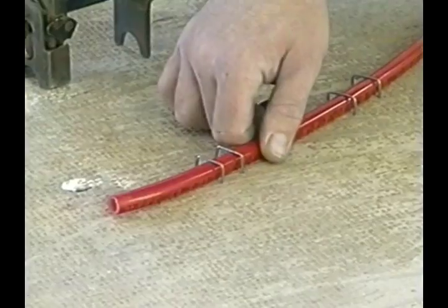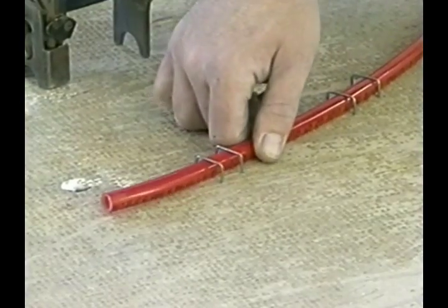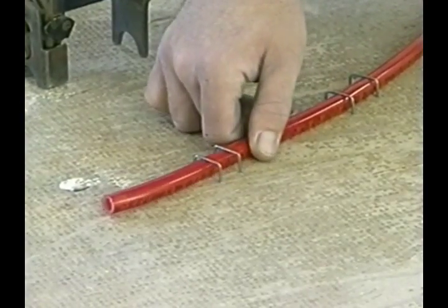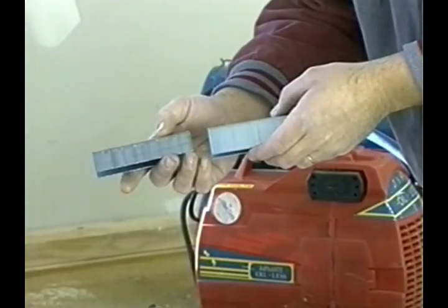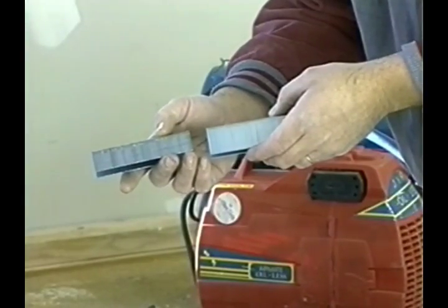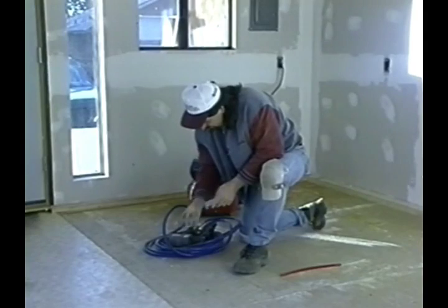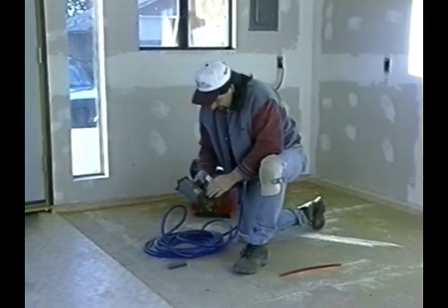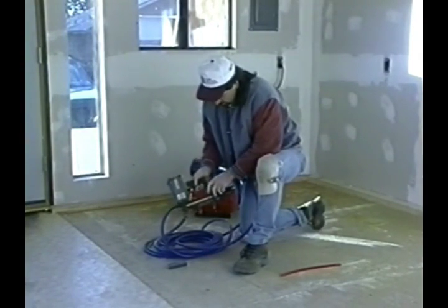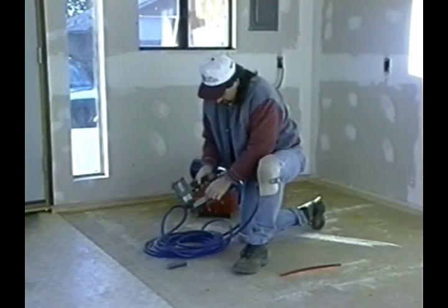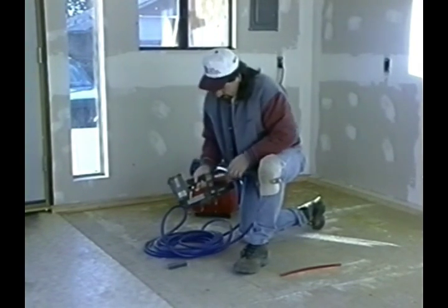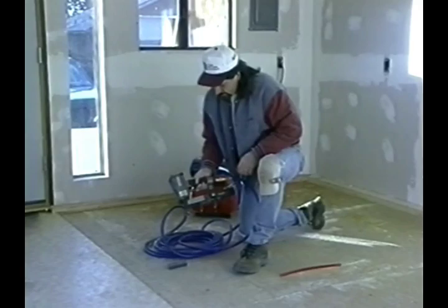It's okay to leave some gap between the tube and the top of the staple, or a slight indentation. Choosing the proper staple is determined by the size of the tubing you're installing. Most common length of staples are 1 1/4 inch length. The width is determined by what brand staple gun you have.